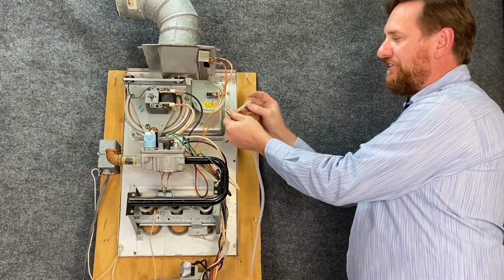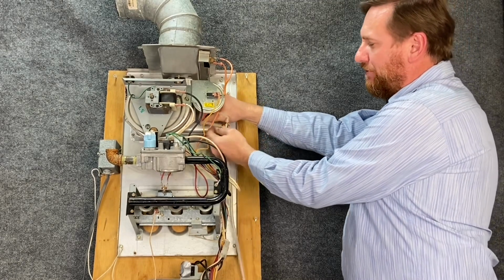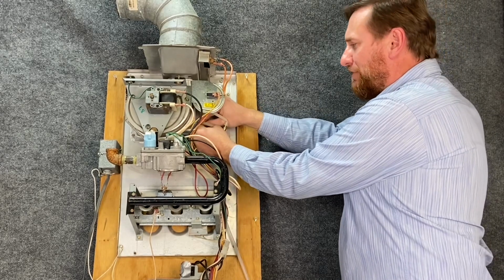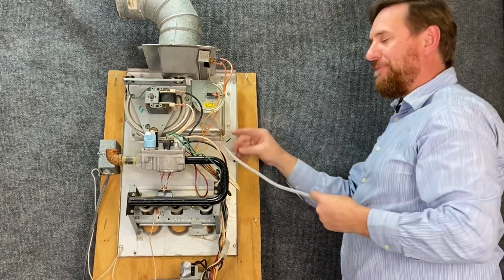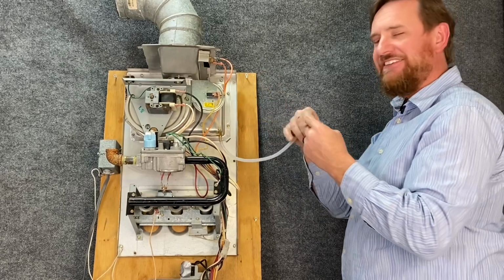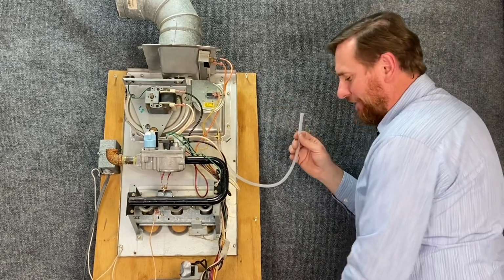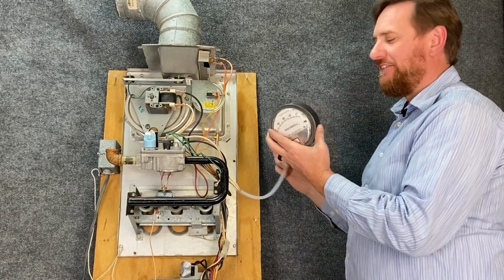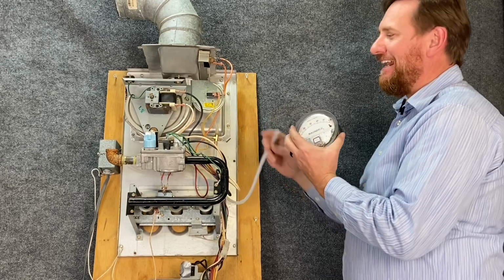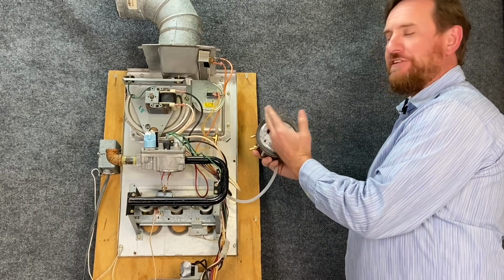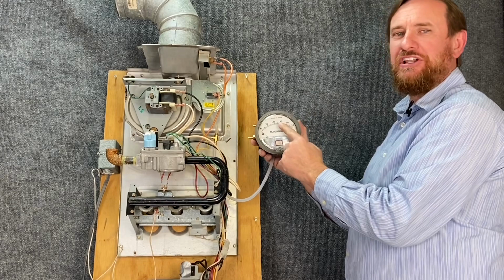The other hose on the side is going to go back to my inducer fan motor, my inducer draft, so it's pulling a vacuum. That's also going to pull a vacuum to this and this third hose. In the old days, we used to use a Magnehelic. I would use the low pressure side, and as this ran, I could see how much of a vacuum it's pulling in inches of water column on this tool.